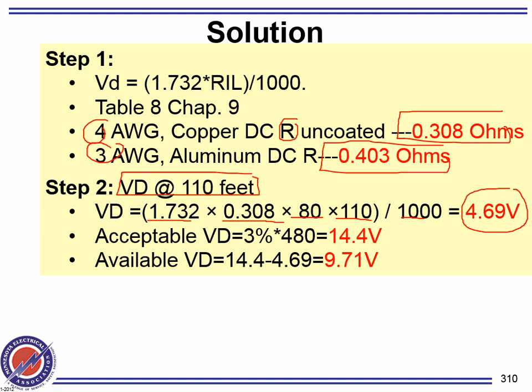Okay, doesn't tell me anything. How much are you allowed to lose on a 480 volt system? You can lose up to 14.4. Now subtract the 4.69 from the 14.4. Now what's my leftover? I lost 4.69. I'm allowed to lose overall 14.4. Gives me an amount of 9.71. Look what happened next.